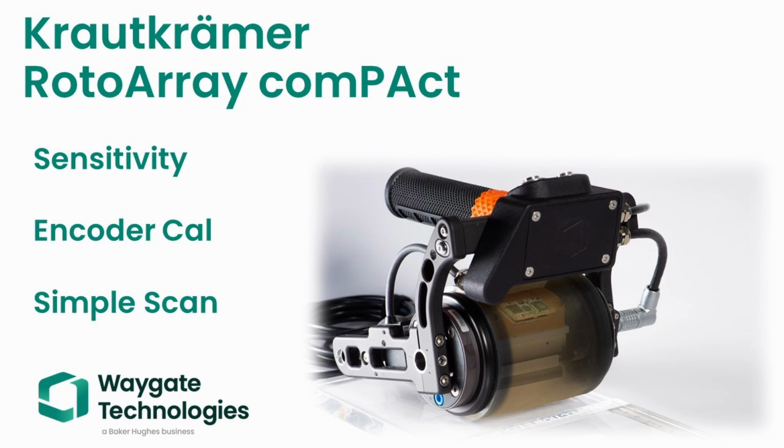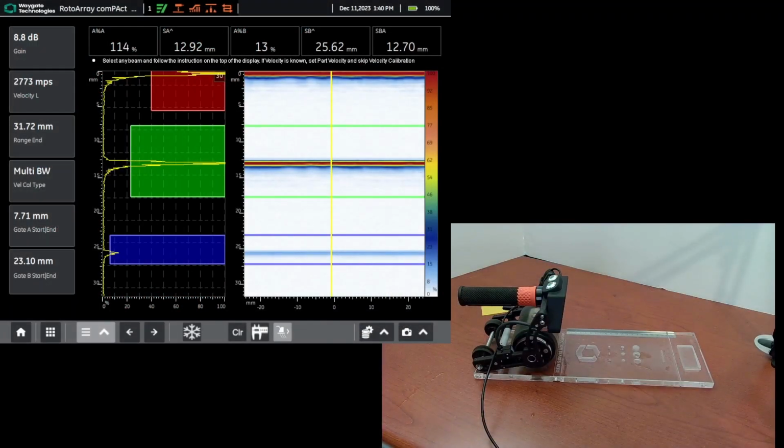We've already connected our instrument. We've checked that all of the elements of the probe are good and ready for use. And we've done our two-point calibration. So in this episode, we are going to walk through doing a sensitivity calibration, getting equal gain or equal sensitivity on all of the virtual probes.